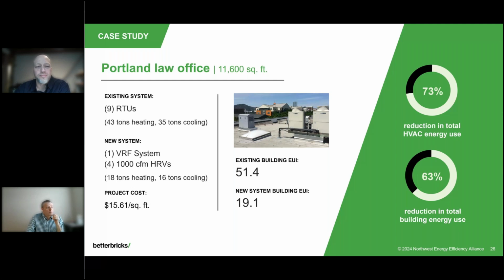So this one's a little bigger building, again in the Portland area. It went from 9 RTUs, 43 tons of heating, 35 tons of cooling, to 1 VRF system, four 1,000 CFM HRVs, and it again dropped the heating load from 43 to 18 tons and from 35 to 16. So again, you cut it in half, right? More than half. And you reduced the EUI from 51 to 19.